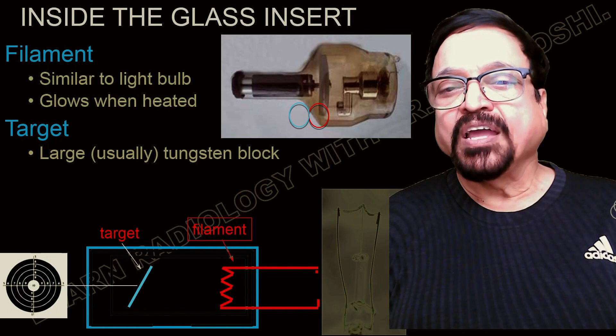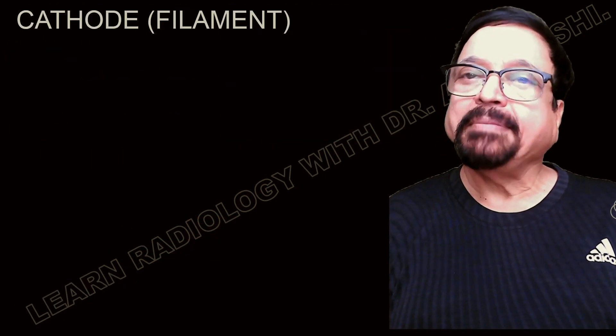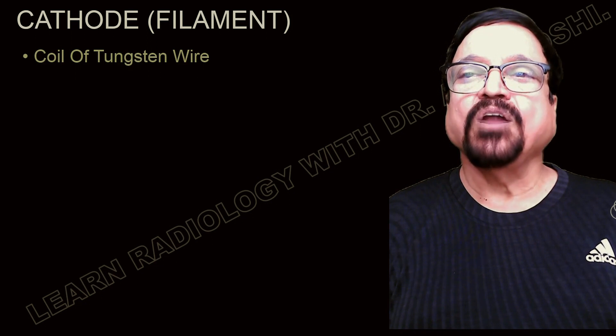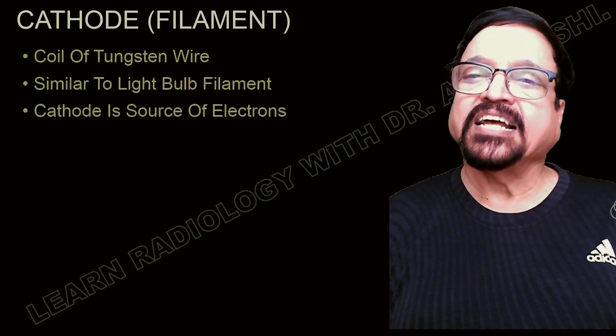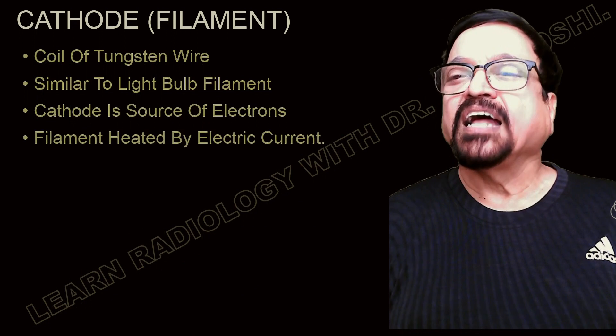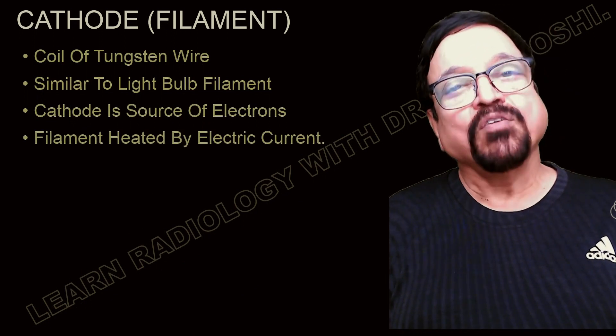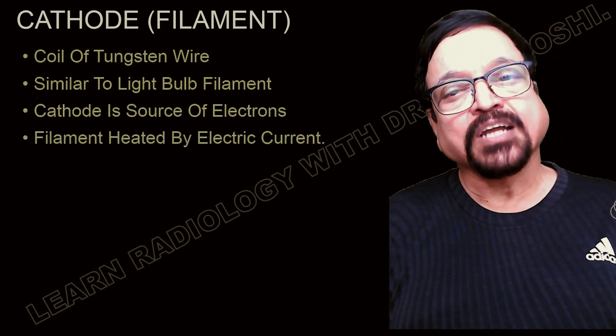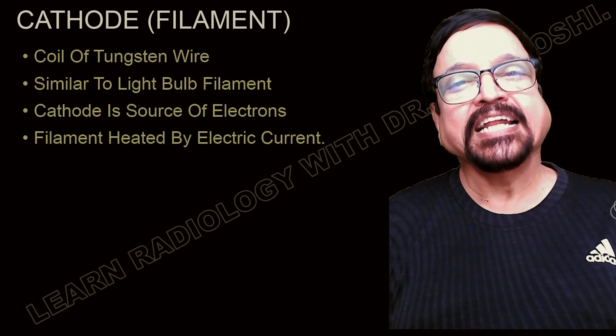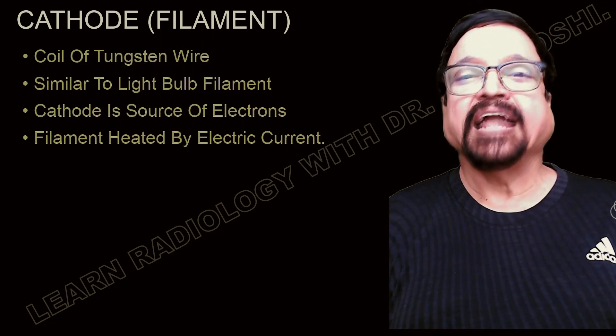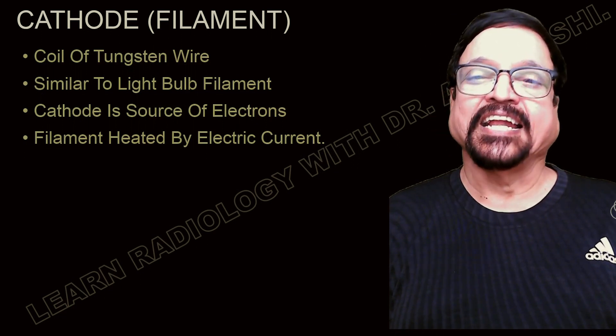Here we have illustrated the filament and the target. The filament is called the cathode. It is a coil of tungsten, similar to that of a light bulb, and is a source of electrons. Because of thermionic emission there is a boiling of electrons which come out due to heat. Electricity produces heat, electrons are boiled out, and they produce an electron cloud which is then accelerated.